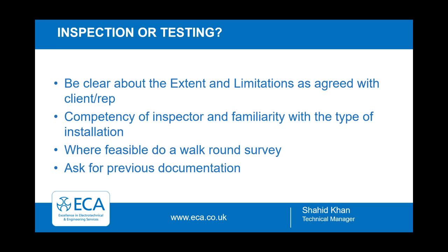A couple of other points to mention are that you should always ask for previous documentation regardless of the type of installation. The quality or lack of records will also give you clues as to the current state of the electrical installation and what to expect. And for complex installations, it's always proven beneficial in my working life to take the time to undertake walk-around surveys of installations before starting the periodic. It gives you a chance to make sense of the installation, decide on a plan of attack, and highlight any areas that you may want to focus on.